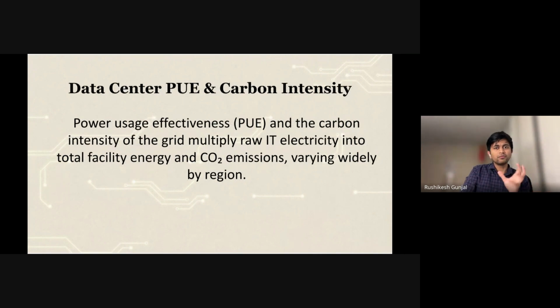When we talk about electricity consumption, it is not enough to look only at the GPUs. Data centers add their own overhead for cooling, power distribution, and conversion losses. This is captured by PUE, Power Usage Effectiveness, which tells us how much extra facility power is required per unit of IT power. A PUE of 1.2 means for every 1 kilowatt hour used by the GPUs, the facility consumes an additional 0.2 kilowatt hour on top.